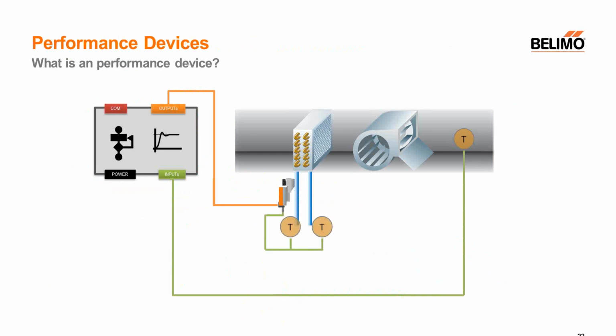So a performance device allows additional information at the actuator to impact that process. So for those of you familiar with an energy valve, this is kind of like an energy valve example, except we're just looking at temperature. So we can make this heat transfer process smarter if we know incoming and outgoing water temperature, so we know the delta T across the coil. And if we set a limit, we could tell the actuator to start backing off when our delta T got below a certain point.